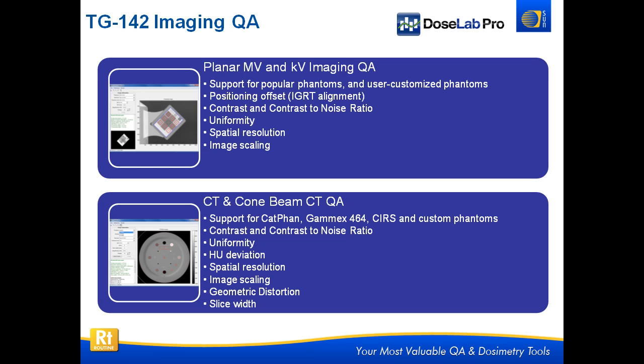We calculate the position and offset for IGRT alignment — you can use the same phantom for positioning and image quality. We calculate contrast and CNR, uniformity, spatial resolution, and image scaling. It's a very complete solution in just basically one button click to load the tool.